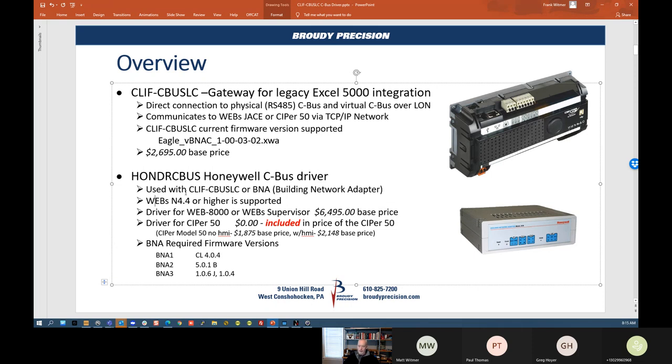The Honeywell CBUS driver is used with the CLIF device and also with the BNA. If you have an existing XL5000 system using BNAs to bring in your network to the existing front end, you could redeploy that BNA and bring it directly into a CIPer 50, a Web 8000, or a Web Supervisor using this Honeywell driver. So if you have a CIPer 50, there is no hardware cost and no driver cost to integrate the XL5000, though you still have your typical field device and field point licensing costs. That part hasn't changed.